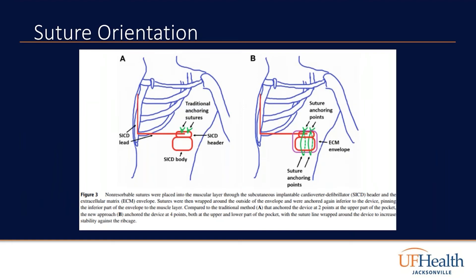You can see here there are two diagrams on the left. In diagram A, the subcutaneous ICD comes with a header that has two holes, essentially, which are traditional anchoring sutures. These traditional anchoring sutures enable one to suture the device superiorly to the muscle.